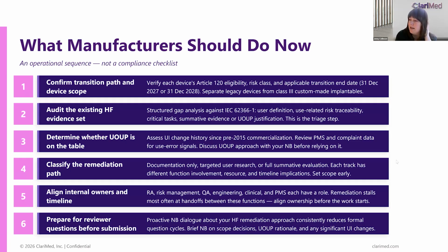I think what I would add to that is that they perform reviews in a slightly different way to people who are used to dealing with the FDA. They're very much applying their rigor to whether you've adhered to a standard. My experience with certain notified bodies is they go through a checklist. Does someone have a use specification?